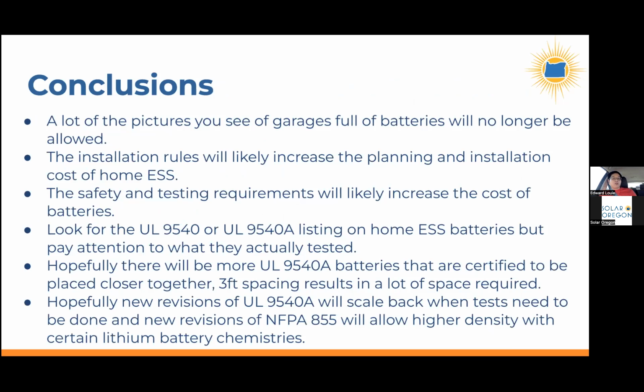The number of tests, like I said, if you put together different permutations, you need to have its own separate UL 9540A test. So these additional test requirements will likely increase the cost of the batteries. But thankfully, the number of batteries that have undergone a 9540A test is actually quite big. All the big name players in the world of home batteries have undergone UL 9540A testing, at least at the module level. The number that have tested it with the units placed close together or stacked, like 3 or 5 or 6 stacked together in a server rack, those tests have not been done yet.